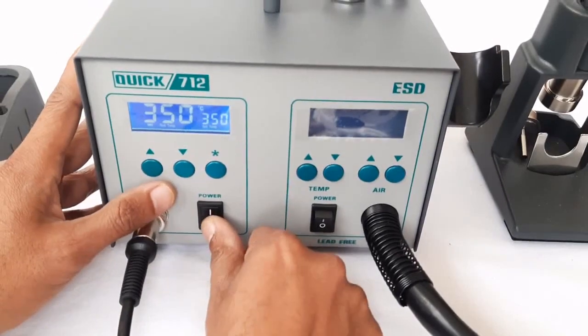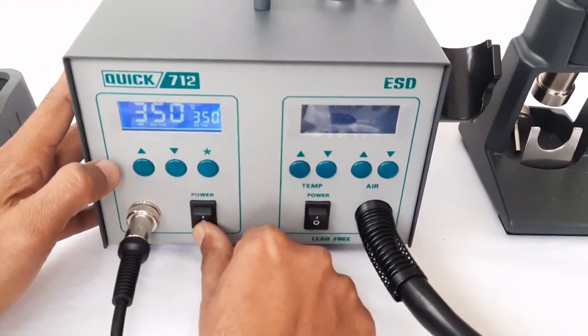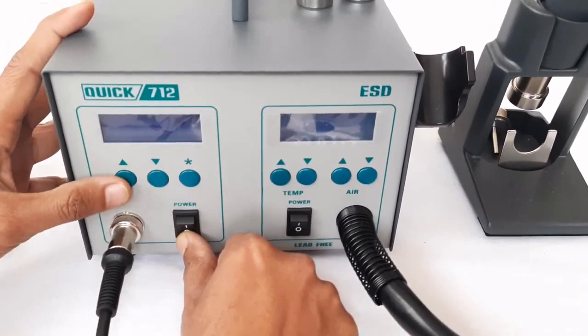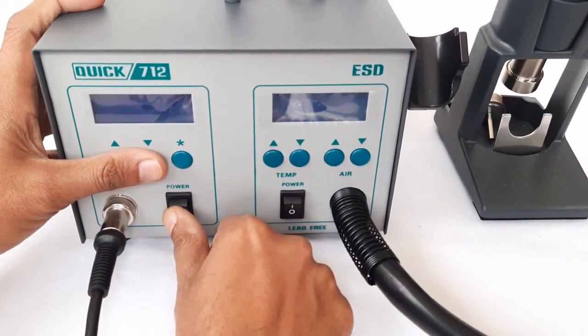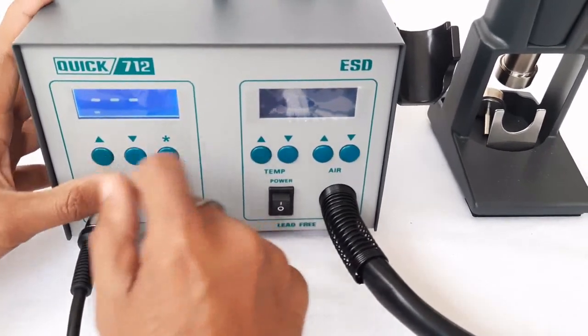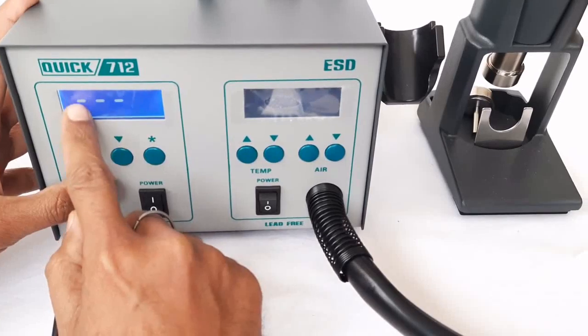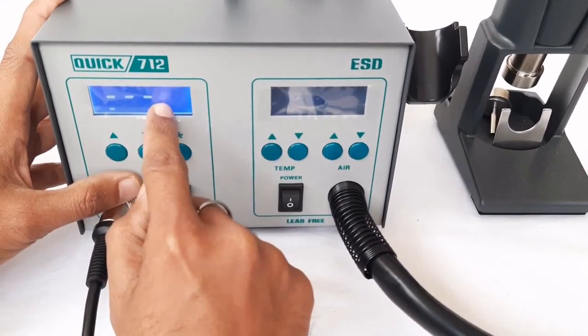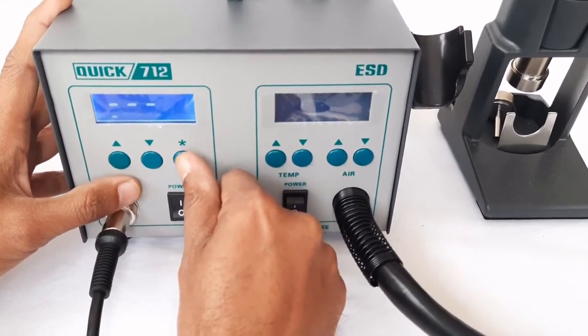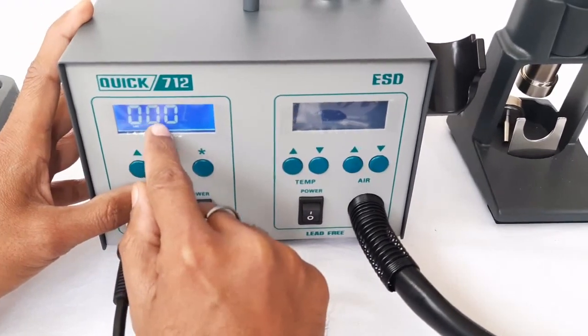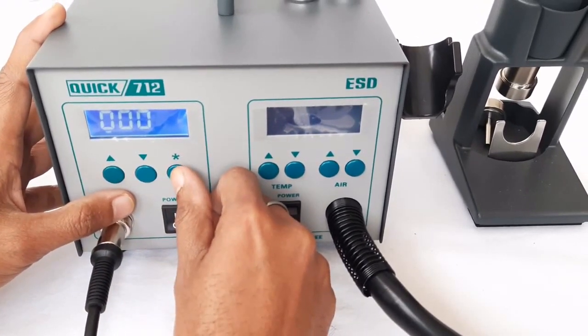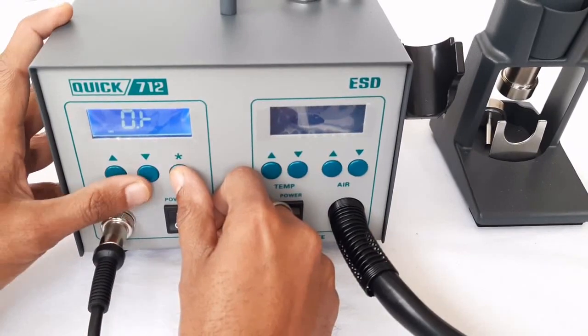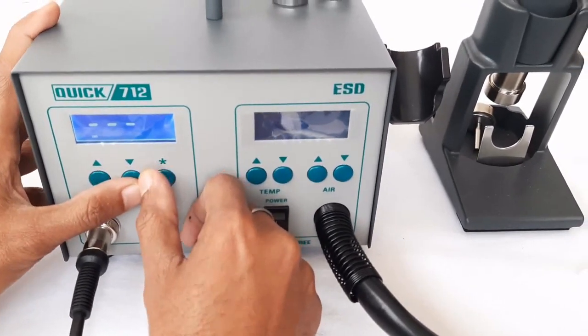First, we need to switch this channel 1 off, then press this up and down button simultaneously and switch the unit on. Now the three dots will be displayed on the screen. First, then we need to press the star button. This 000 is the default password.